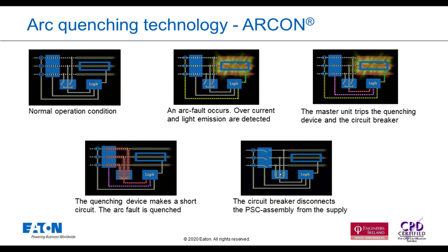Just a note for you guys. The tests during 61641 are done with doors and covers all closed and screwed onto the assembly. The Eaton ARCON device has been tested to 61641 with the doors open, and we still achieve criteria 1 to 7. That's an additional safety aspect that Eaton have taken on board in terms of testing and costs, to demonstrate that even with the door open, with the ARCON installed in our switchgear, we're still meeting criteria 1 to 7, where other manufacturers are testing with doors closed and covers on. Just something to bear in mind.